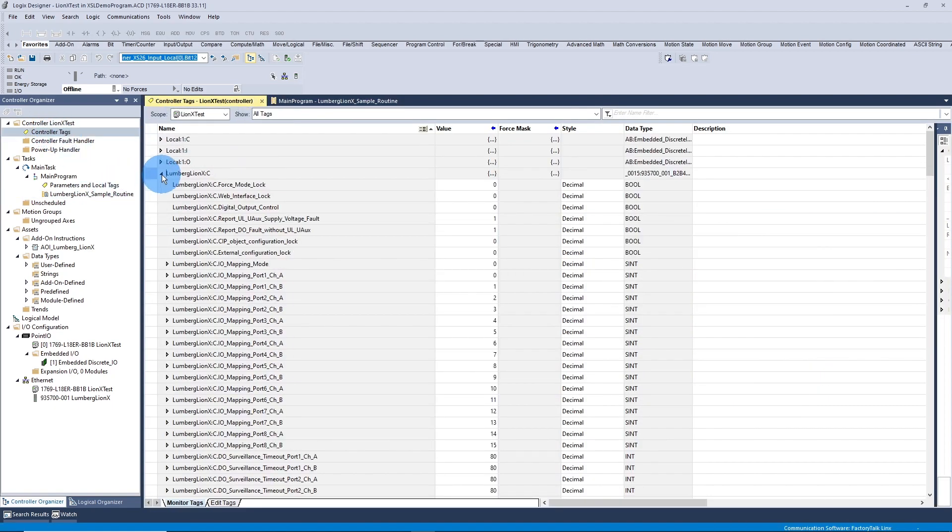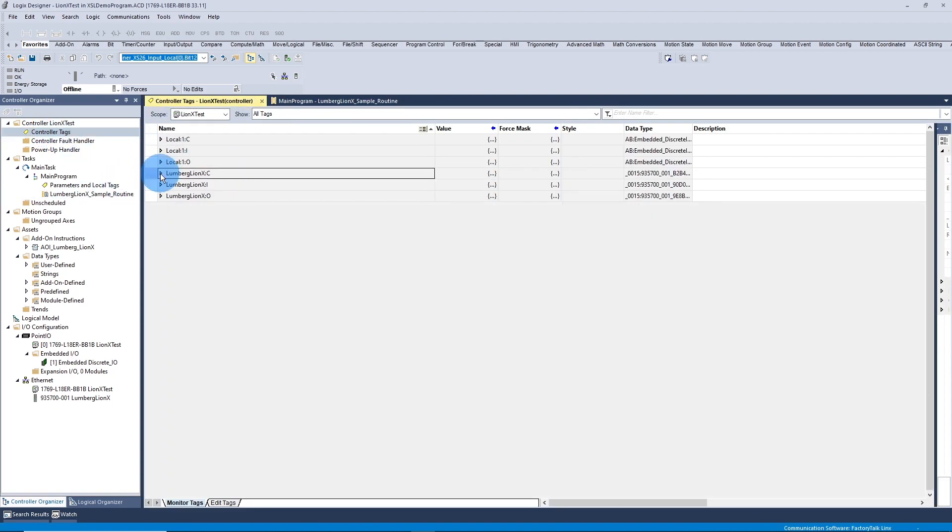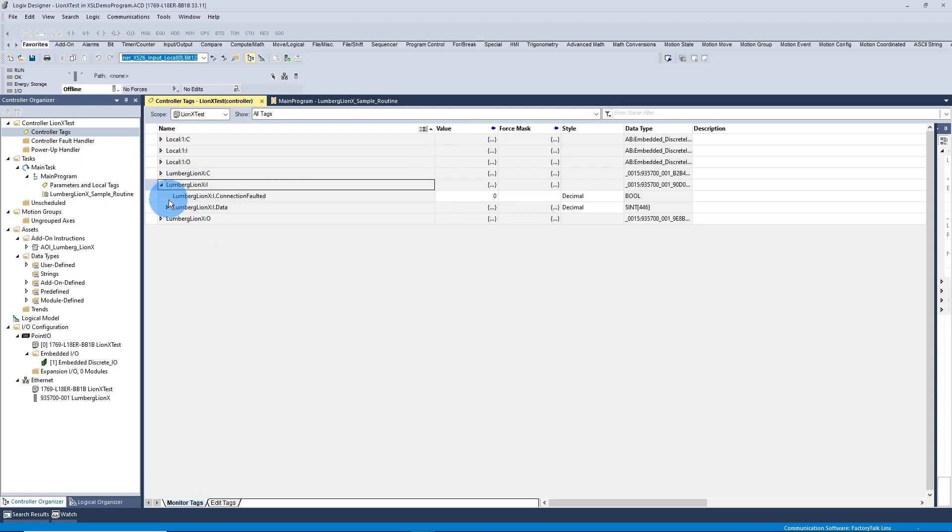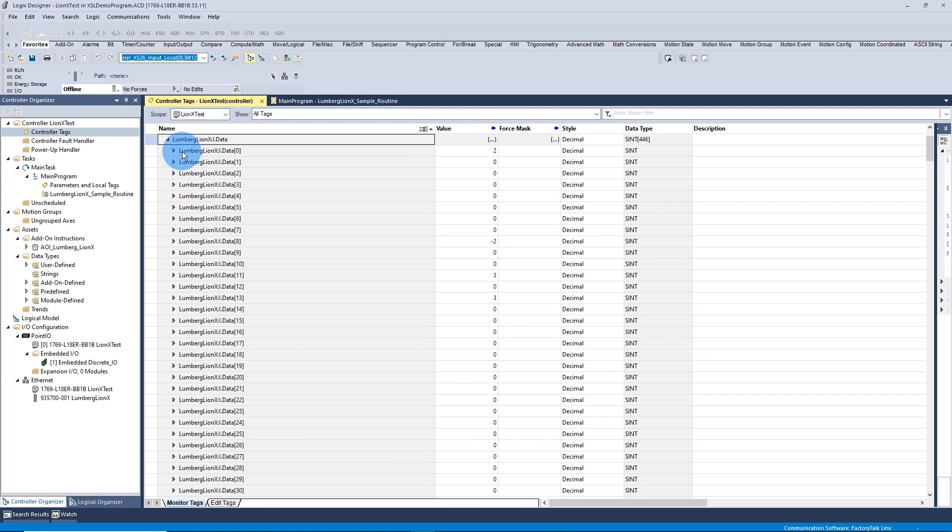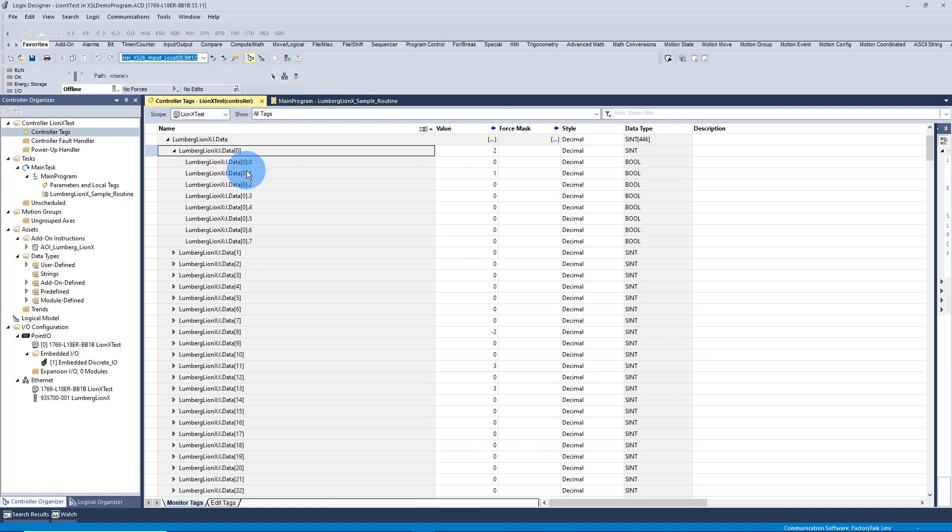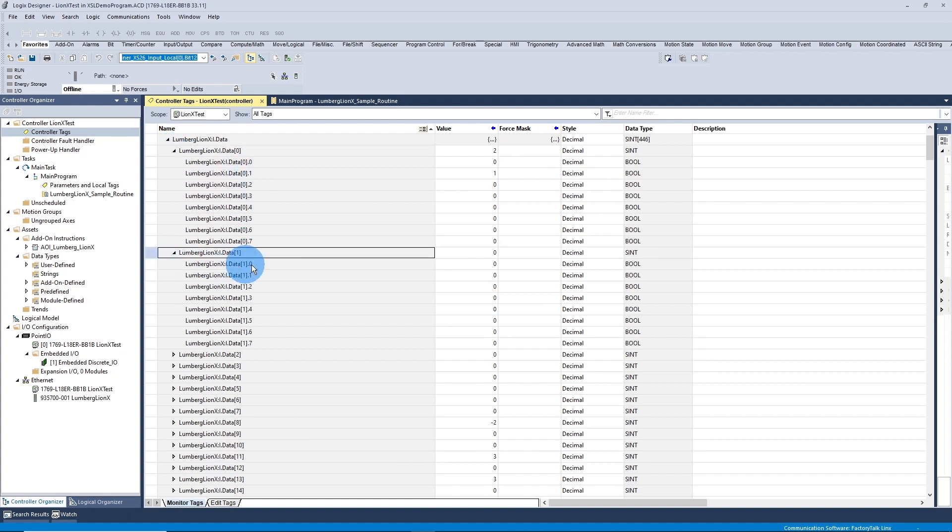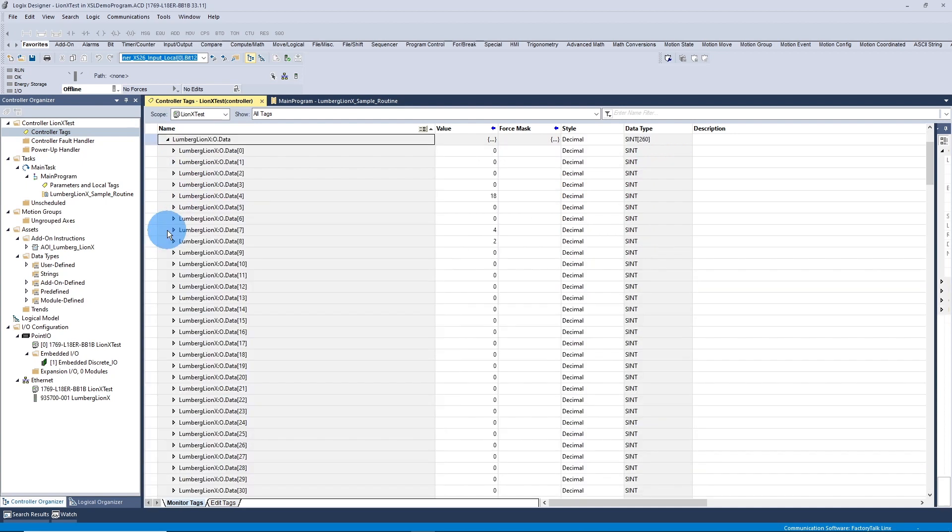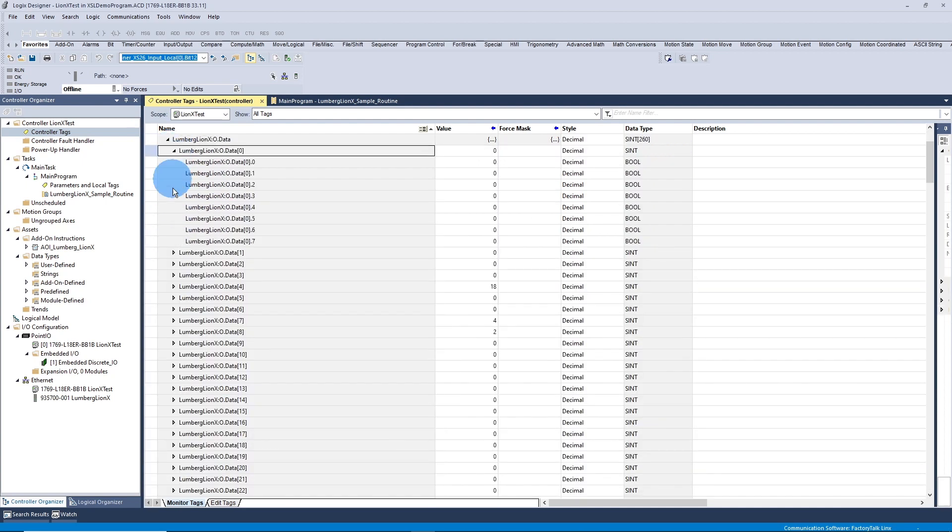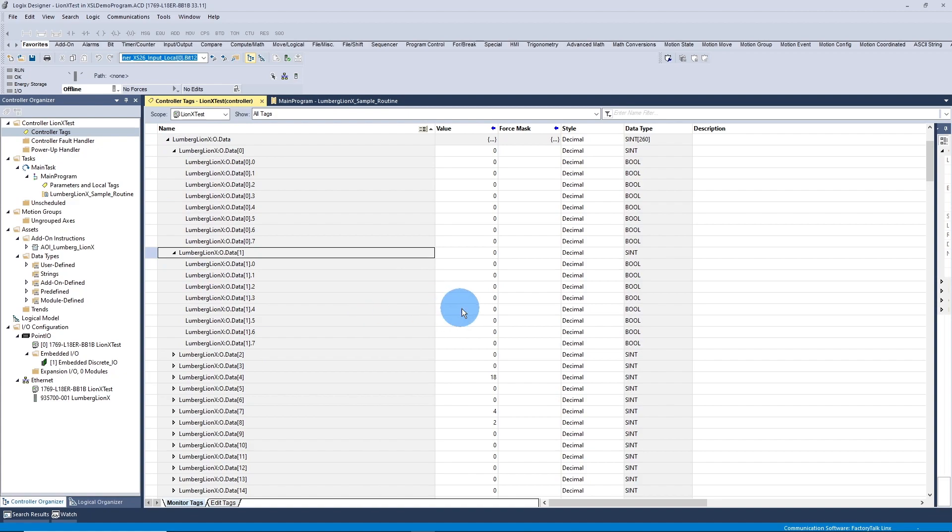And then to find where your digital input and digital output data is, if you go to the Lumberg line, your tag data, the input side, under data, the first 16 bits will be all your digital inputs. And same goes for outputs. If you're controlling any outputs, it's going to be the first 16 bits are your digital outputs.